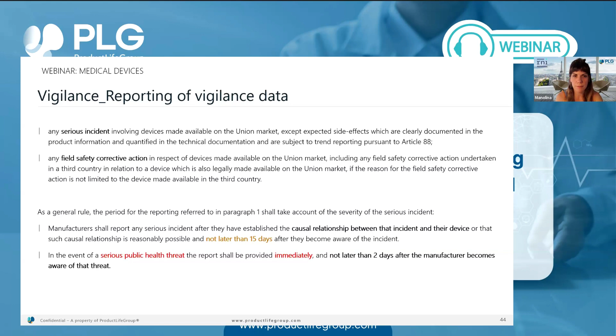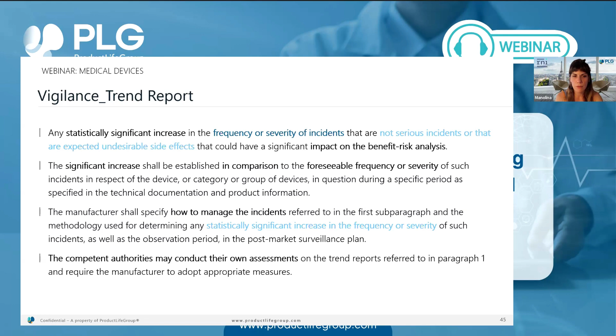Now, about the trend reports: what should be documented is any statistically significant increase in the frequency or severity of incidents that are not serious incidents, or that are expected undesirable side effects. These incidents can have an impact on the benefit-risk analysis. This significant increase should be established in comparison to the usual frequency or severity of these incidents, and the manufacturer should specify how to manage these incidents and determine any statistically significant increase in their frequency or severity. The competent authorities may conduct their own assessments of these trend reports and, if required, inform the manufacturer of any appropriate measure.